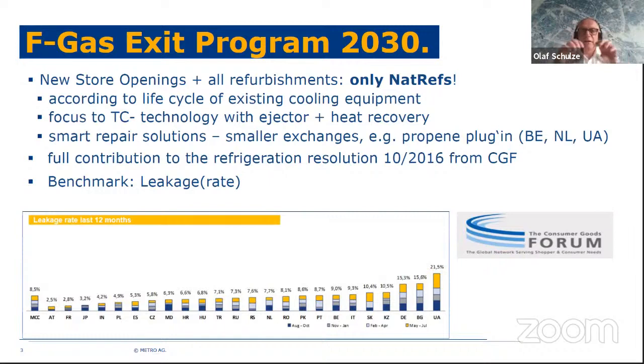And the benchmark, and it is not new, the benchmark is leakage, right? The problem is not the HFC in the equipment, the problem is the HFC in the leakages. And unfortunately it is part of the honesty, we have actual last running 12 months leakage rate by 8.5%. Next year, by the way, we will come below 8%, but we have the 8%. And here you can see from the left side for Austria, 2.5, till the right side, 20, so 10 times more in the end, or 8 times more, more than 20% in Ukraine. They are the real leakages that we are measuring in the last 12 months.